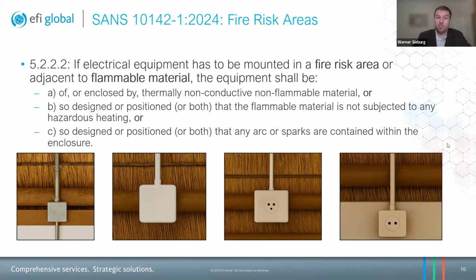So it is obviously a non-flammable material, but it is certainly not thermally non-conductive. Okay. And so number A actually requires that it must be thermally non-conductive and non-flammable. And so the heat conduction from an electrical fault in such a box would probably cause pyrolysis of the wooden structure behind it, and perhaps also then of the thatch above it.